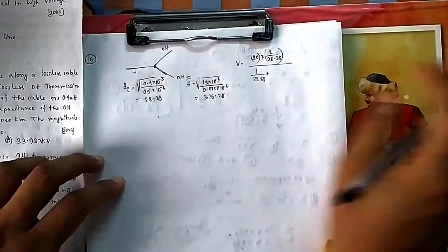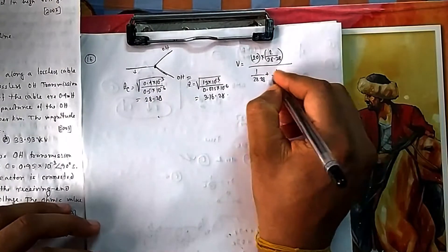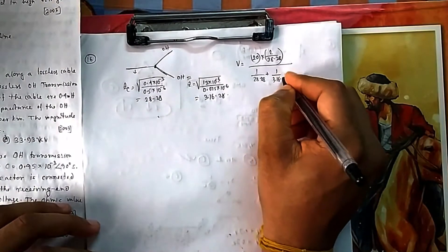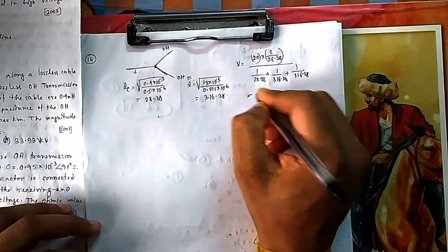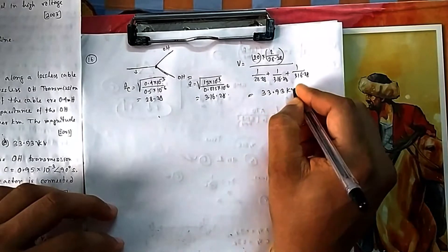There are different cases: terminating with infinite, open line, short line, or terminated with another impedance. Putting in the values with 316.28, you will get 33.93 kV. That is option D.